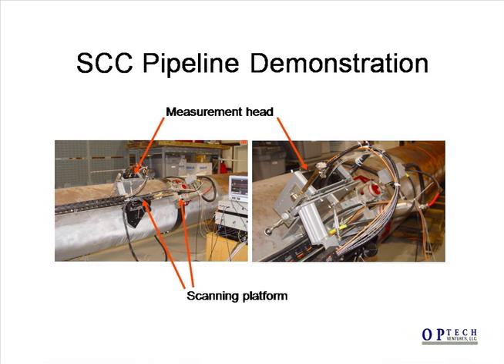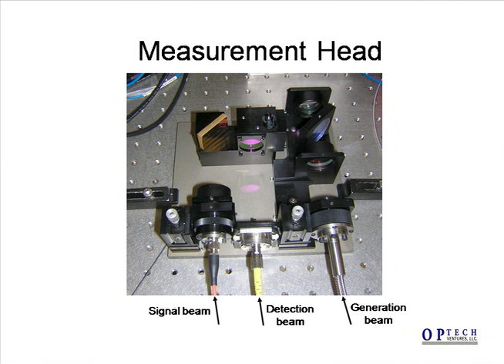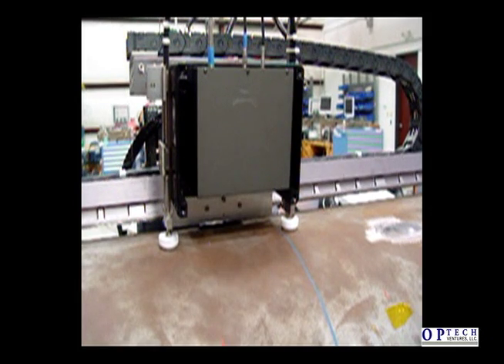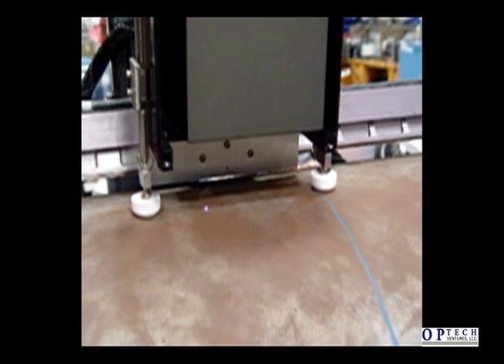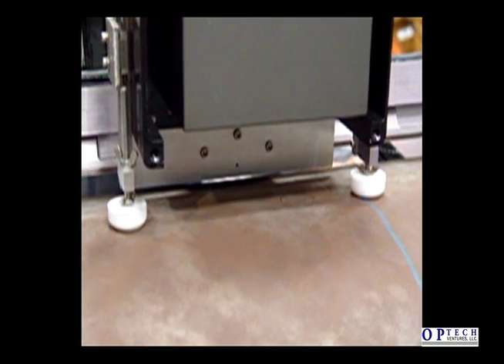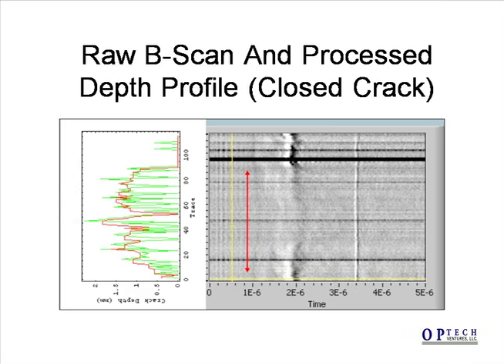We participated in an industry demonstration of a scanning laser ultrasonic system in Houston, Texas. A measurement head was mounted in a motorized platform that could be scanned axially and circumferentially. Since the cracks are mostly axial, this was the common scan direction. Our measurement head was only about 7 inches on a side and was fully fiberized. In this video, we see our head scanning a single crack. The detection beam is at a wavelength of 1550 nm and so it is not visible in the video. We show a raw B-scan of one of the scanned cracks along with the crack profile as provided by our signal processing algorithm.